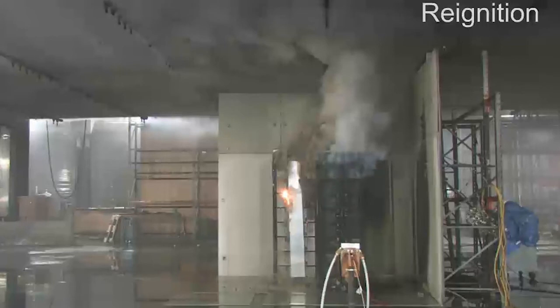And so we let that sit for about a half an hour, sprinklers on, and then we came in with our water monitors, and because this is the test lab, we had all of our protection equipment set up. We sprayed water essentially through a fire hose directly at that rack to try to cool it off for quite a while. Once we thought we were in a good spot, we wanted to get rid of all that water from the air, let the smoke spread out, and see what was left, see if that fire had in fact extinguished.